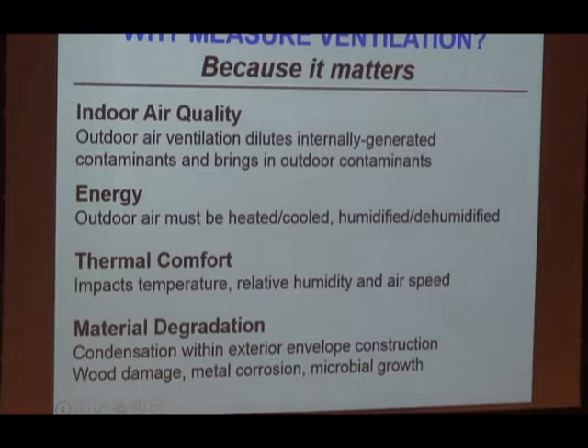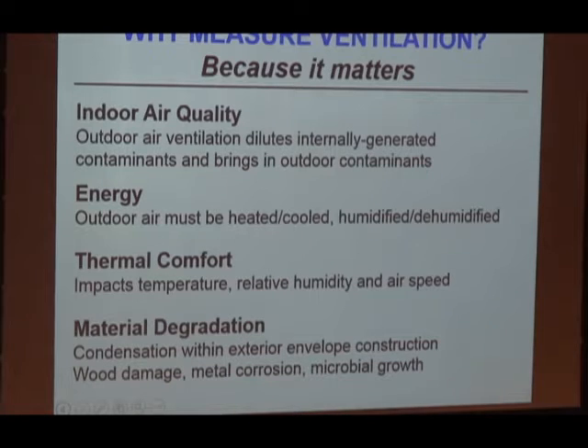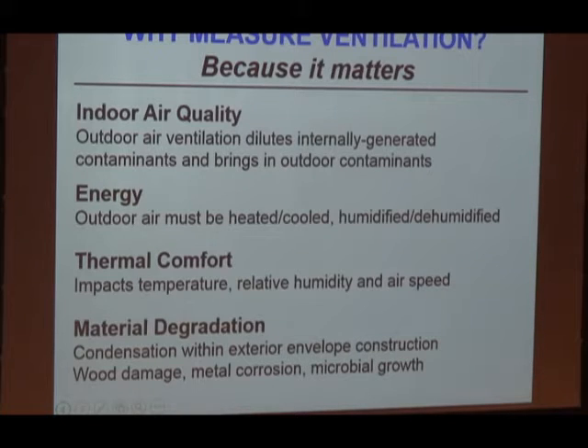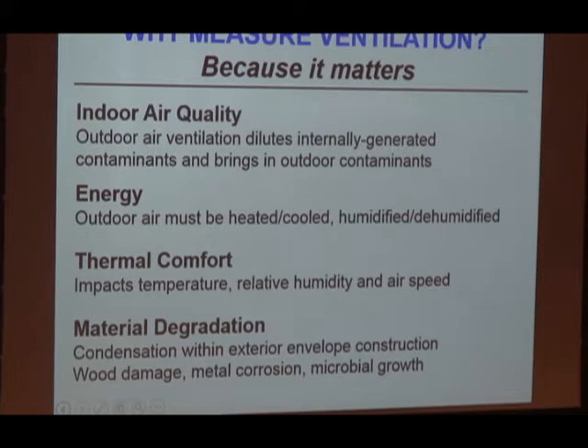Thermal comfort is another reason — ventilation rates impact those indoor environment parameters. Finally, the materials in a building and the building envelope can be impacted by ventilation rates depending on how air is brought in, how moisture is dealt with, and the interactions between airflows and the envelope. You can increase the likelihood of microbial condensation leading to microbial growth, as well as corrosion of metals, if these considerations aren't well handled.